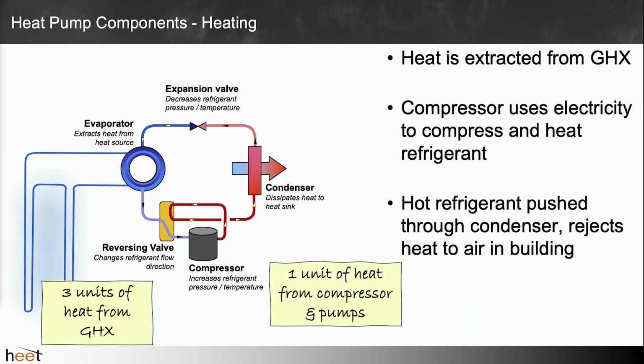That electrically powered equipment generates heat as well, right? That's your power input, that compressor. There's also the circulation pump and fans. And then you give those 4 units of heat to the building, right? So that hot refrigerant is pushed through the condenser and then rejects that heat to the air in the building.